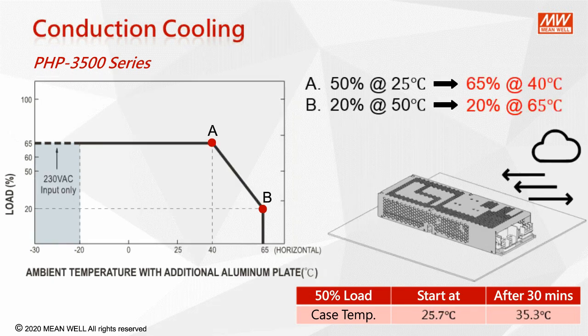Now let's look at the conduction cooling performance. A cooling plate has been added to the bottom of the PHP 3500. The power supply can now output more power at higher temperature. Point A has increased from 50% at 25 degrees Celsius to 65% at 40 degrees Celsius. Point B has increased from 20% at 50 degrees to 20% at 65 degrees Celsius. If we operate this setup with the same output power as before, after 30 minutes, the same case temperature increases to 35.3 degrees Celsius, which is only 9.6 degrees of temperature rise.